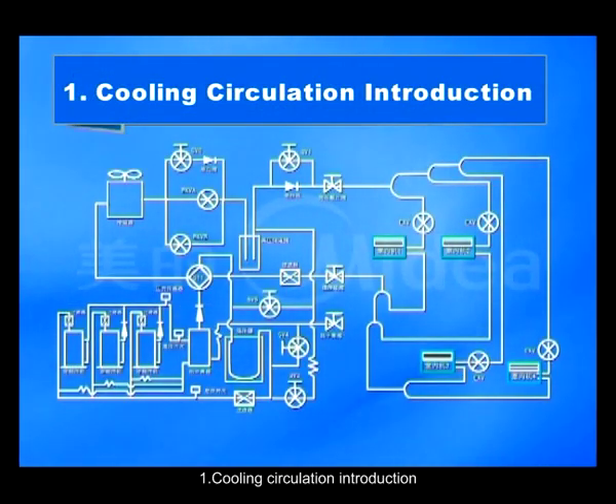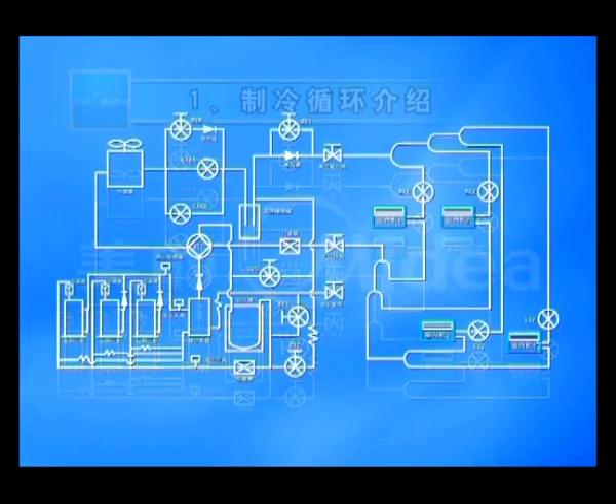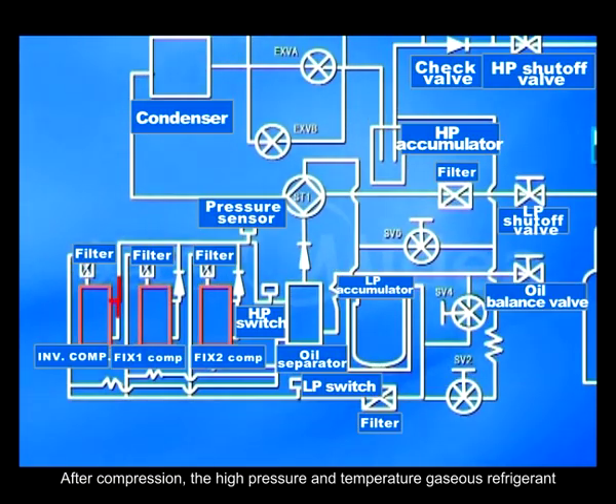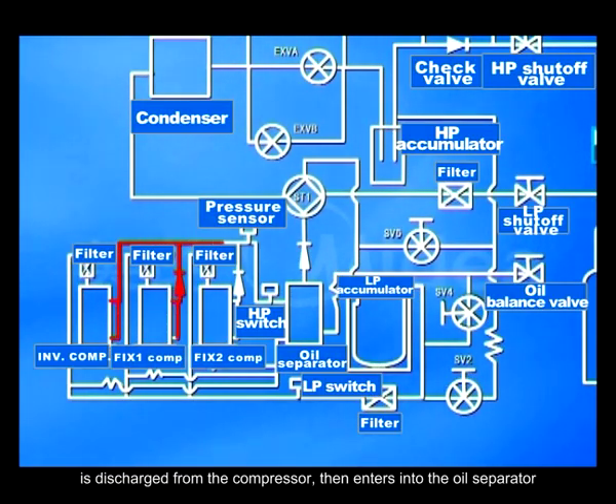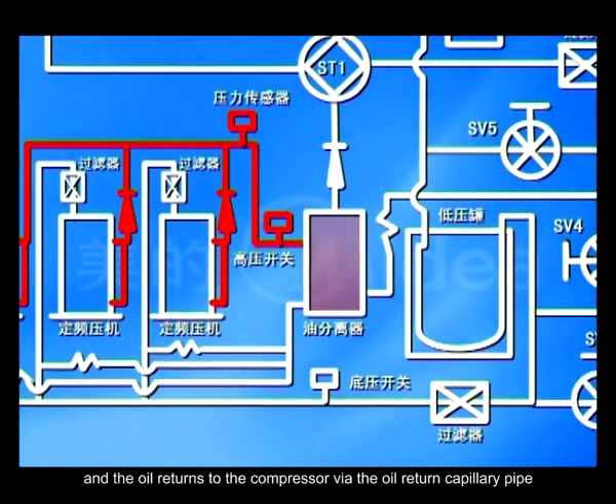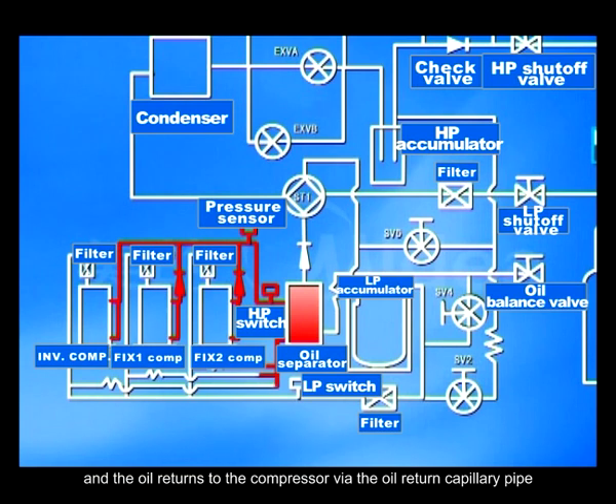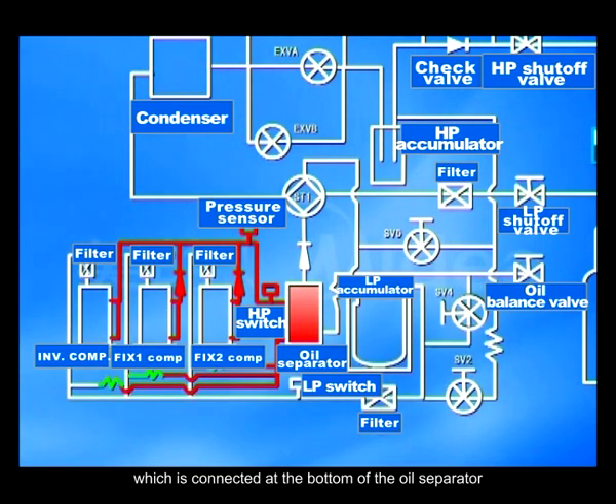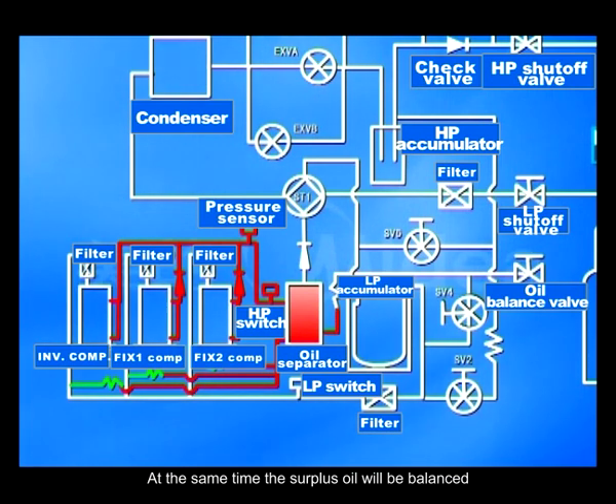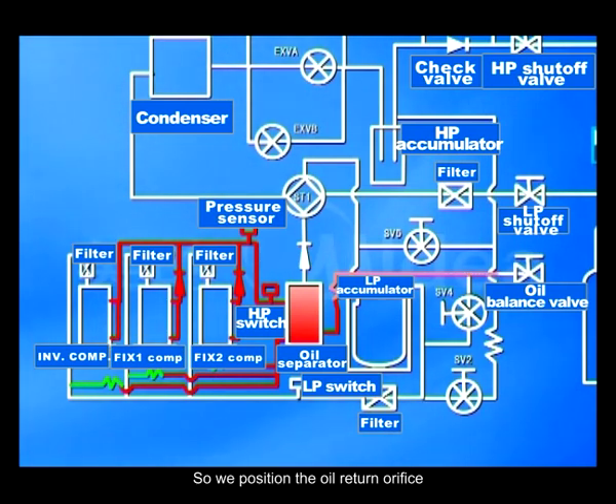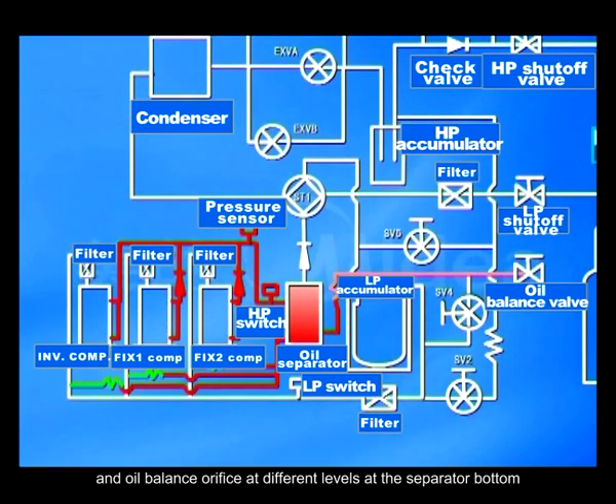1. Cooling Circulation Introduction. After compression, the high pressure and temperature gaseous refrigerant is discharged from the compressor, then enters into the oil separator. Refrigerant and oil is divided by the oil separator, and the oil returns to the compressor via the oil return capillary pipe, which is connected at the bottom of the oil separator. At the same time, the surplus oil will be balanced to the other combined compressors by the oil balancing pipe. So we position the oil return orifice and oil balance orifice at the different levels at the separator bottom.